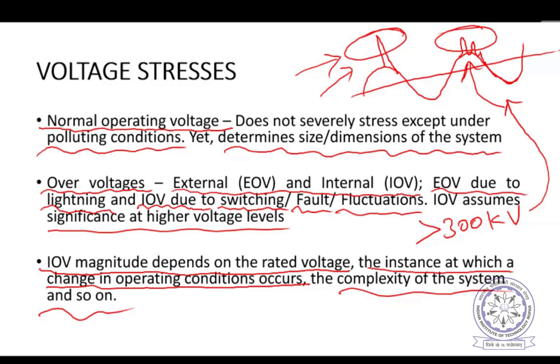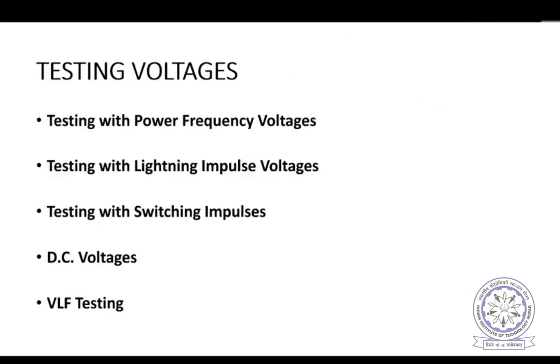So there are certain testing voltages. Based on these over voltages, we need to test the power system equipment before installation or even during the manufacturing process also. So there are several testing voltages. Now, testing with power frequency, which is the same as operating voltage frequency. We test at a little bit higher voltage so that it will survive for some 30-40 years.